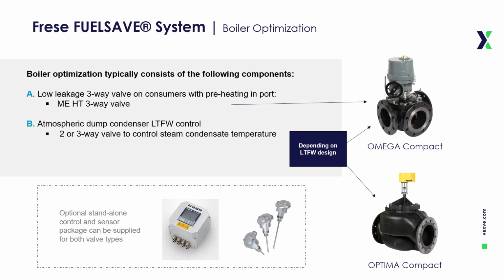Boiler optimization within the Frese FUELSAVE system is achieved through a combination of precision valve technology and intelligent control strategies. The first key element is the low-leakage three-way valve, installed on consumers requiring preheating while the vessel is in port. For example, the main engine high-temperature three-way valve ensures stable flow and temperature control during preheating cycles.